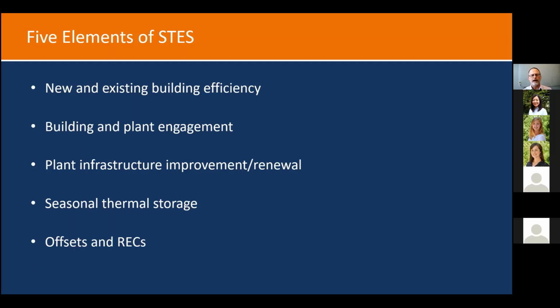In order to drive the use of these new and emerging heat-generating technologies that can displace fossil fuels, we might ask buildings to have a higher, artificial cooling load, so it can load up my heat recovery chiller to make heat. In wintertime, we might use exhaust air in buildings with 100% outside air or large air movement, driving some chilled water off in coils in those buildings in order to make my plants run more efficiently. That's the concept of building and plant engagement.